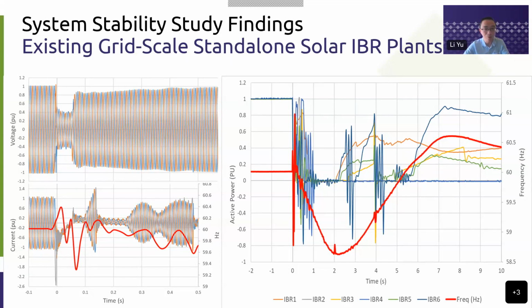During the fault, we can see the IBR basically going into momentary cessation mode. After the fault got cleared, it stayed in momentary cessation mode for around 1 to 2 cycles. After that, the IBR started trying to increase current. However, something happened that made the IBR give up that attempt, and we see very minimal current output around the 0.2 second mark. Then the IBR tried one more time and still failed. In this 0.5 second time frame, we start seeing frequency drop to around 59.6 hertz. But during this whole process, this IBR plant does not show any support.